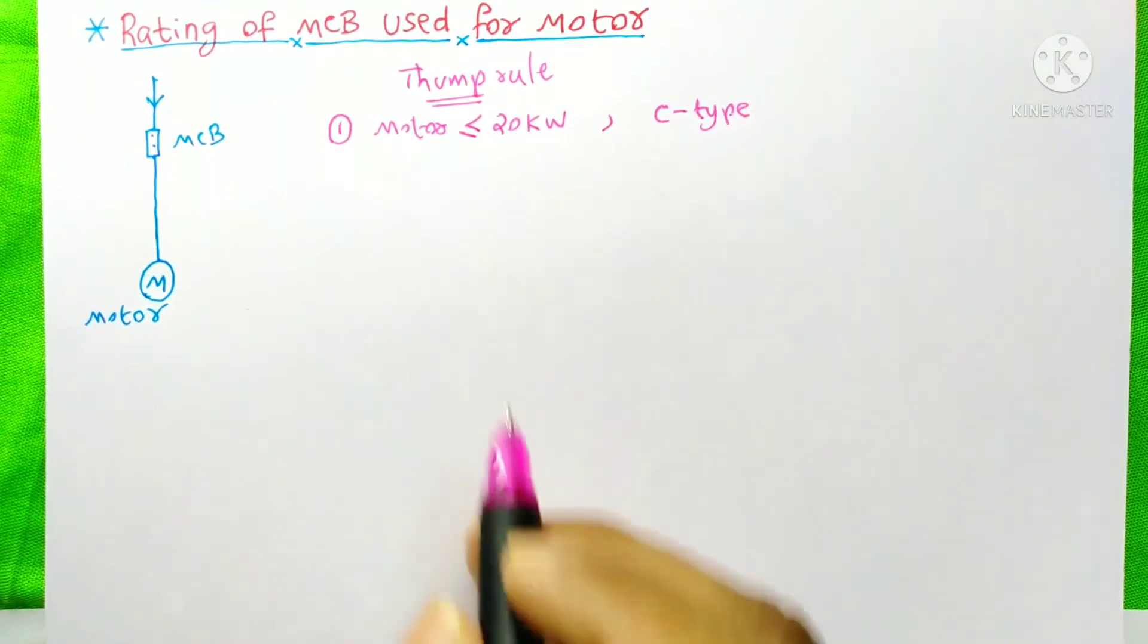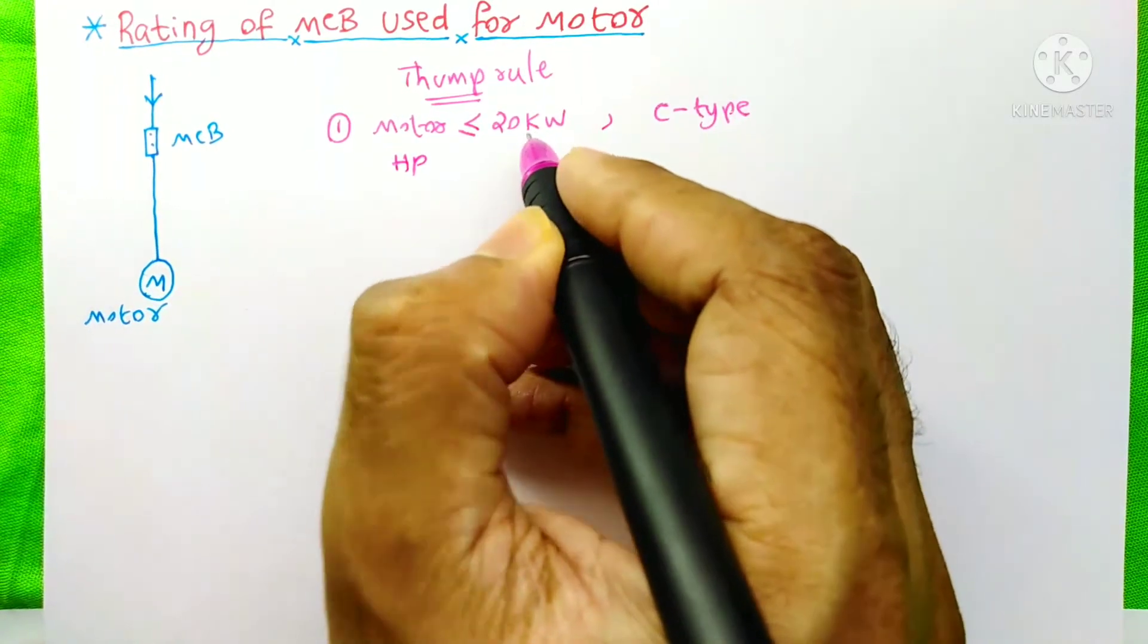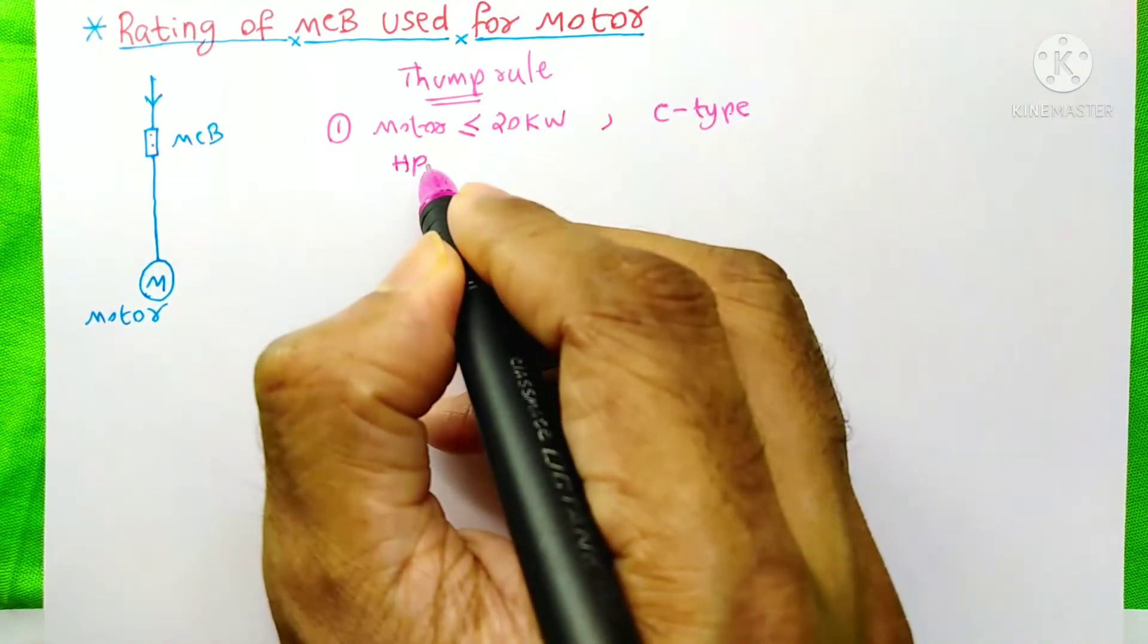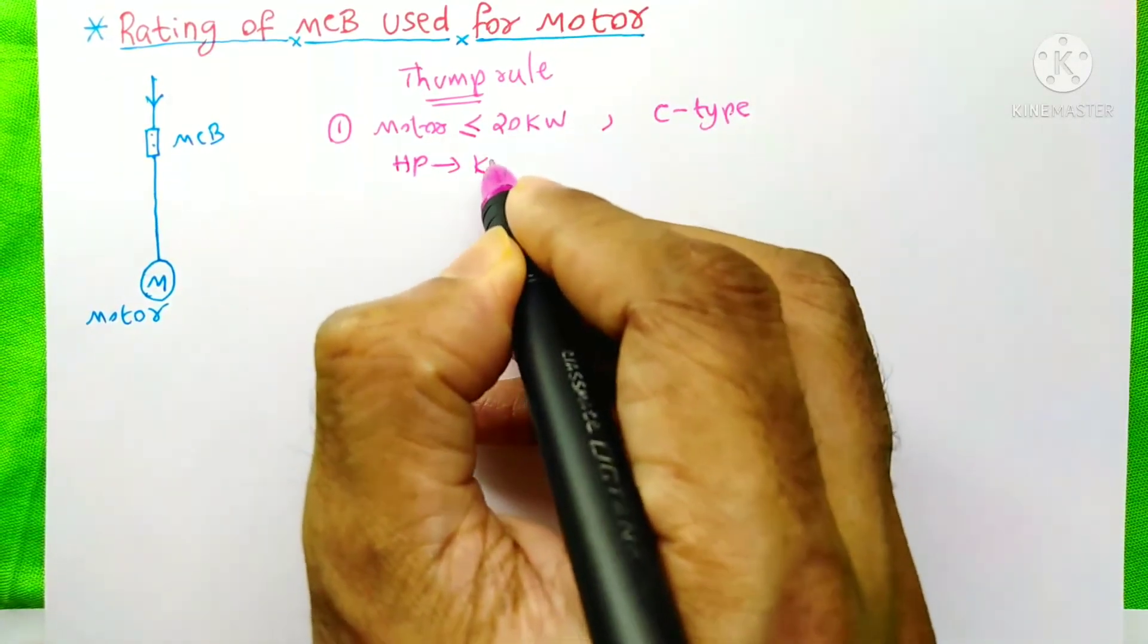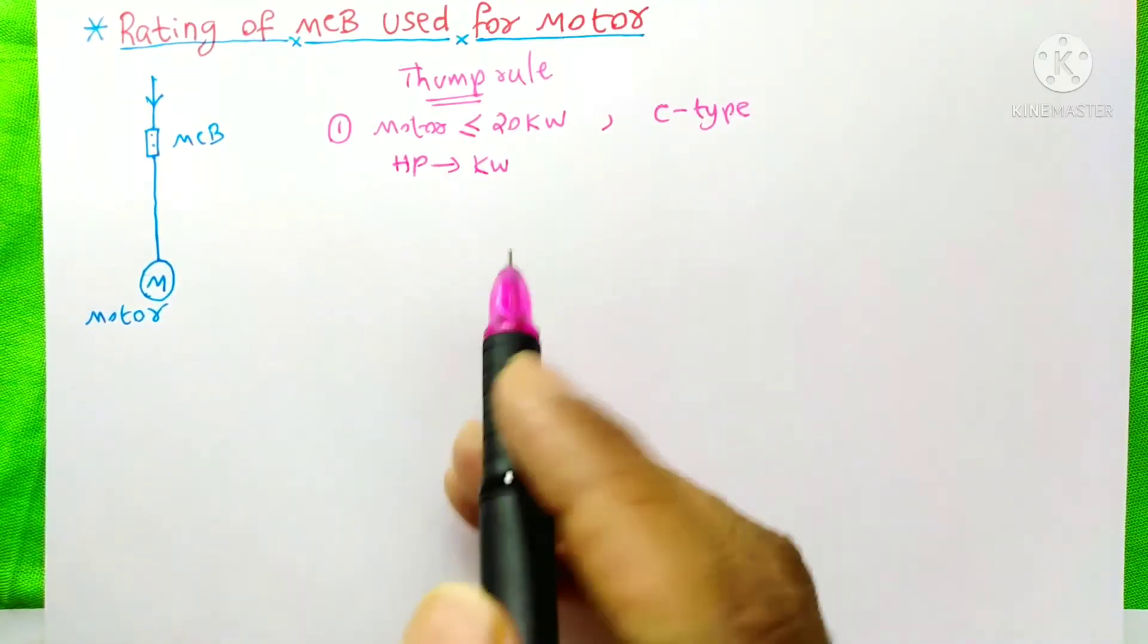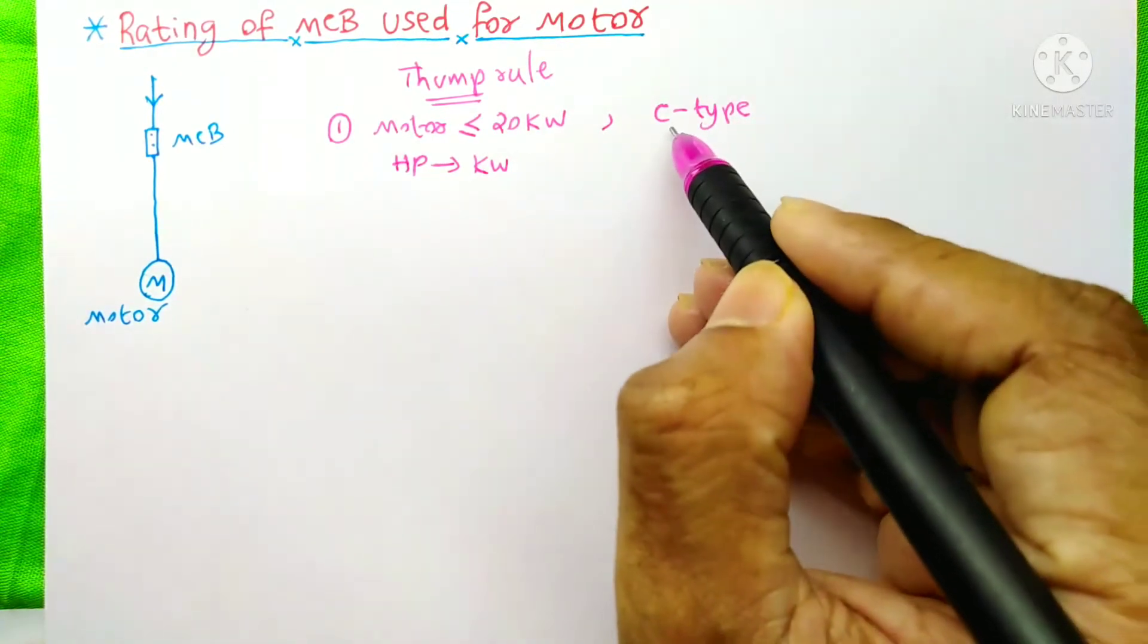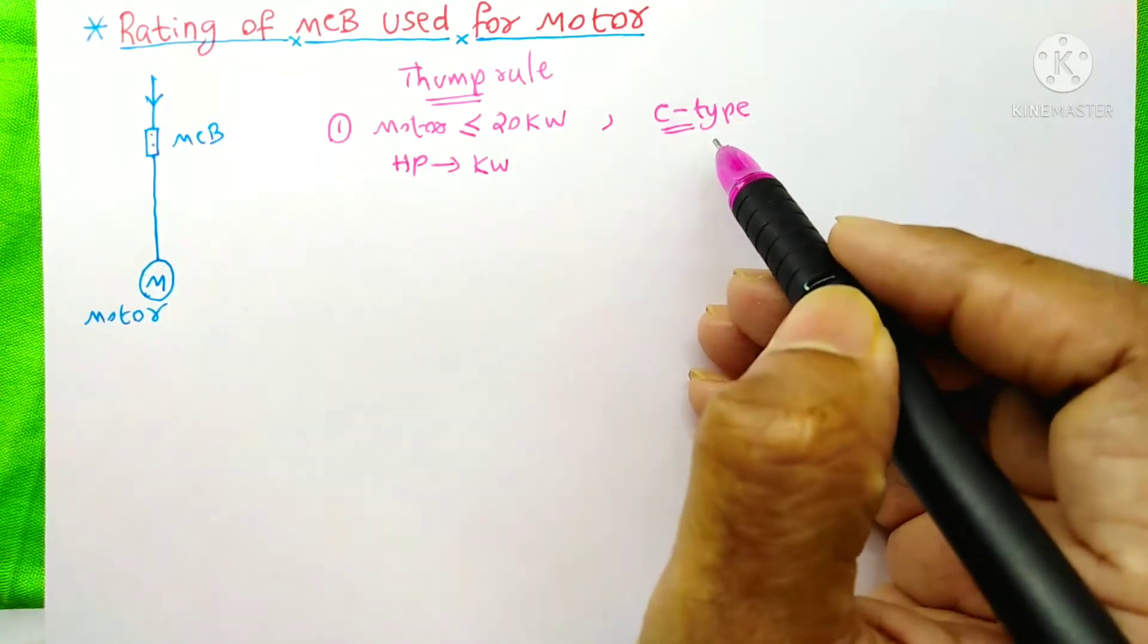We know that most of the motors are rated in HP, not in kW. So first you need to convert this HP to kW and if this kW is less than or equal to 20kW, then you need to select the C-type MCB for your purpose.